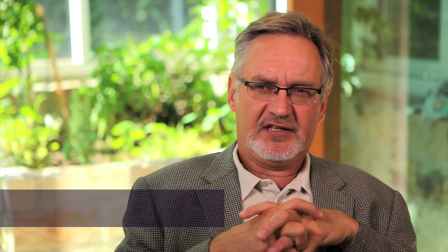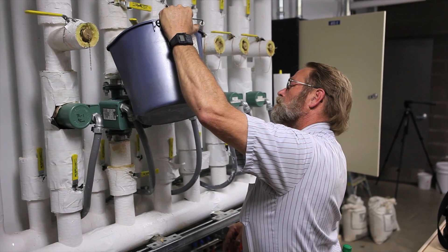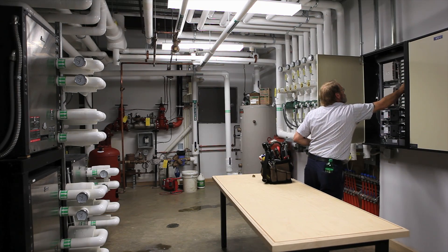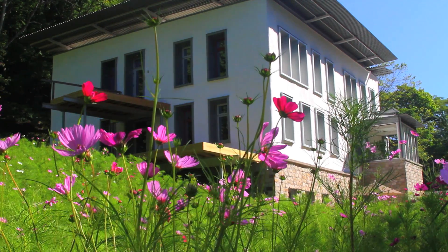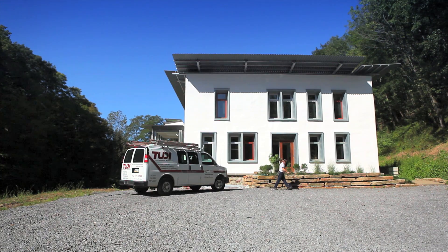We tried something new here which is called radiant cooling. Radiant heating has been done quite a bit in the Pittsburgh area, but no one has ever done radiant cooling. Moving water through pipes is ten times more efficient than moving air through ducts. Our geothermal well field takes the cool water that comes out of the earth, mixes it, and puts it through pipes in the concrete here, cooling that floor slab to about 70 degrees, which gives us a nice indoor temperature of about 74 degrees. It's the least expensive and most energy-efficient way you can cool a building. This building will use about 25 percent of the energy of a very typical high-performance office building, so we've really driven down the energy cost quite a bit.